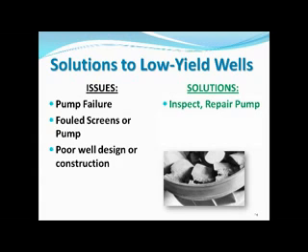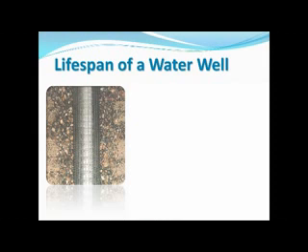If the pump is working fine, perhaps the well screens are blocked or fouled. This will require an aggressive treatment and cleaning procedure, again by a licensed pump installation contractor. It's not a bad idea to have somebody inspect your well other than the person that installed it. We have encountered things like well screens placed at different depths other than what the construction records indicated. If it wasn't built properly, then there may be some repairs that can be done to improve it.